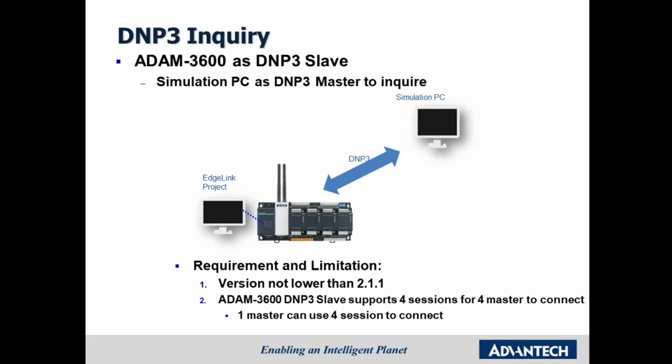Some requirements and limitations here: the version of EdgeLink cannot be lower than 2.1.1. Only above 2.1 do we support DNP3. And limitation number 2, ADAM3600 DNP3 supports only 4 sessions and 4 masters to connect to it. So one master can use at most 4 sessions to connect.